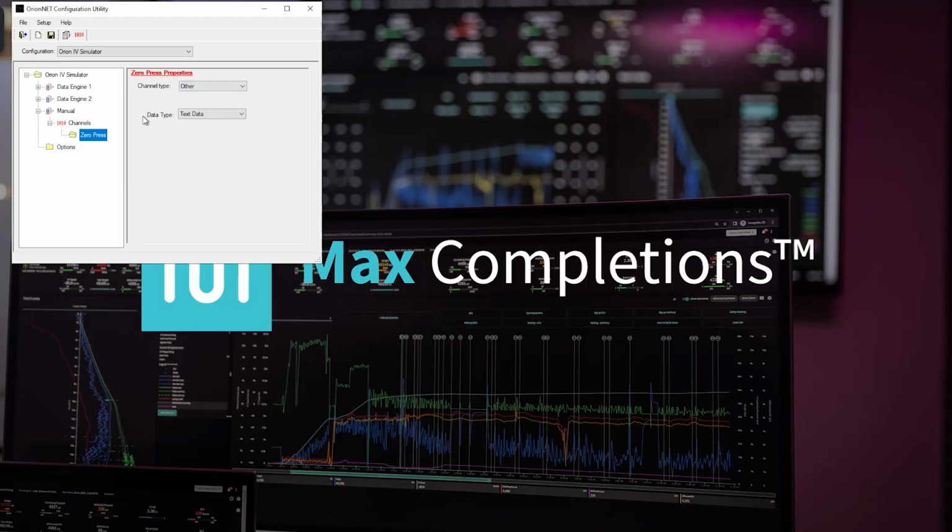Channel type remains as Other. Data type will be changed to numeric data. The low scale, change it to -10,000. For the system units, we will select PSI. Click Save. You have now added 2 new data sources with a new channel under each data source.